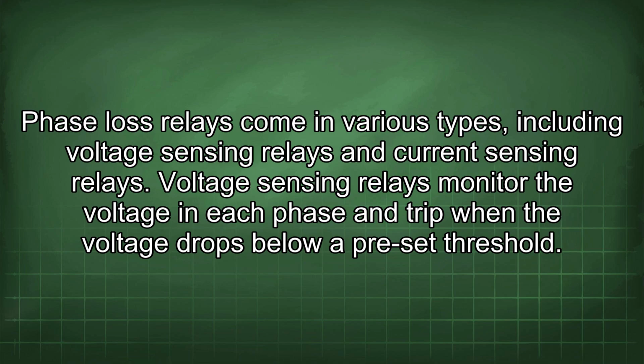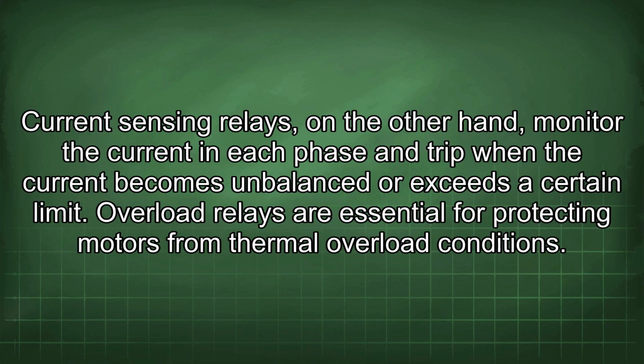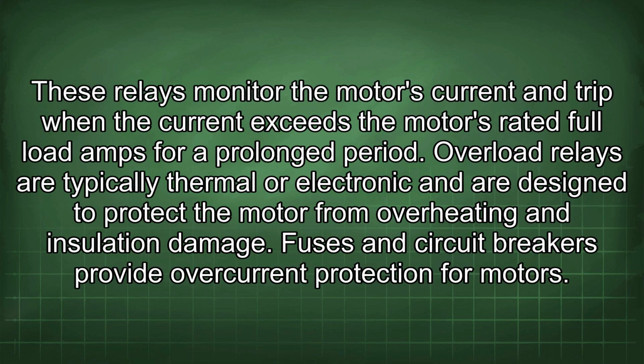Phase loss relays come in various types, including voltage sensing relays and current sensing relays. Voltage sensing relays monitor the voltage in each phase and trip when the voltage drops below a preset threshold. Current sensing relays, on the other hand, monitor the current in each phase and trip when the current becomes unbalanced or exceeds a certain limit. Overload relays are essential for protecting motors from thermal overload conditions. These relays monitor the motor's current and trip when the current exceeds the motor's rated full load amps for a prolonged period. Overload relays are typically thermal or electronic and are designed to protect the motor from overheating and insulation damage.